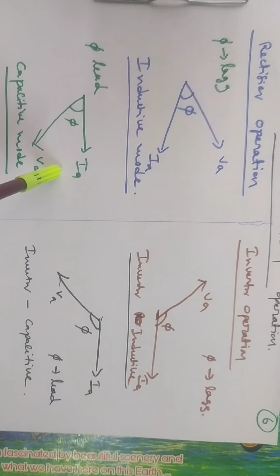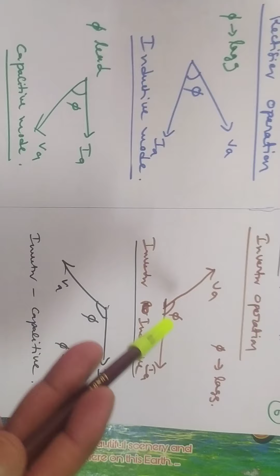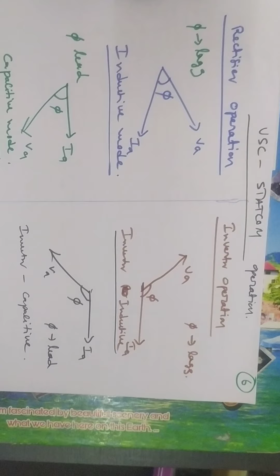So, in a nutshell, the VSC operates as a STATCOM in 2 modes, the rectifier mode and the inverter mode. In the rectifier mode, you have the inductive mode as well as the capacitive mode. Therefore, in the rectifier mode, it is capable of supplying lagging reactive power as well as leading reactive power required by the system. In inverter mode also, it is capable of supplying lagging as well as leading reactive power. The voltage and current phasor relationships are like this in both modes. In the rectifier mode, generally, the angle between VA and IA in both lagging and leading modes is less than 90 degrees. In the ideal case, it is 90. Similarly, in inverter mode, the angle between VA and IA is more than 90 degrees in both inductive and capacitive modes, and in the ideal case it is 90 degrees in both the rectifier and inverter modes.